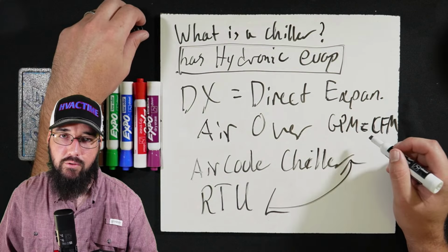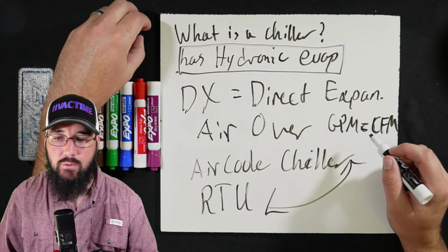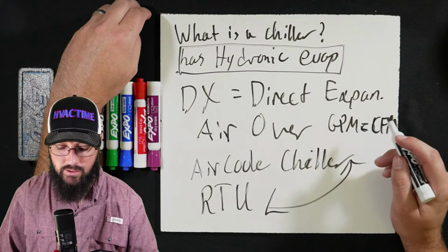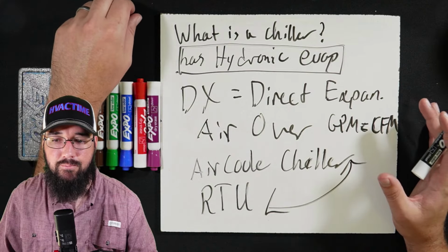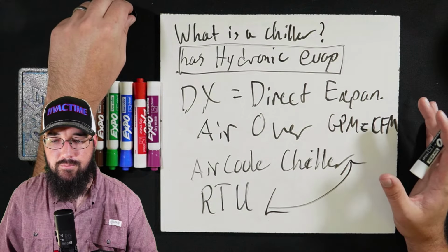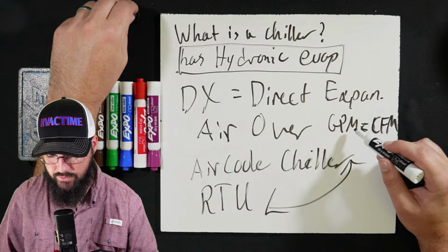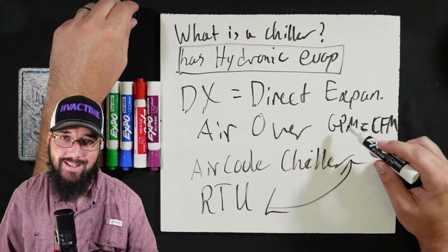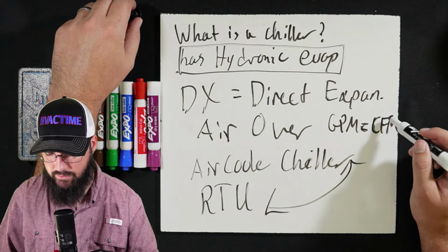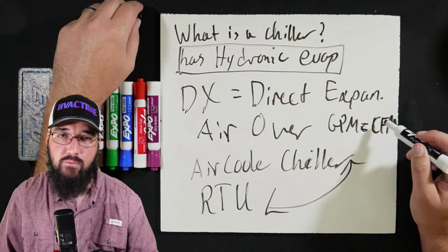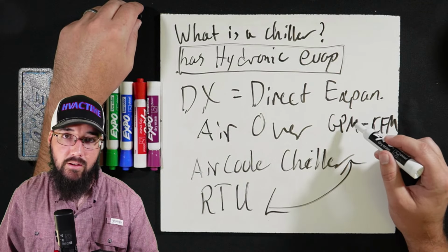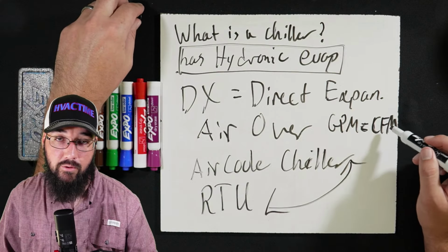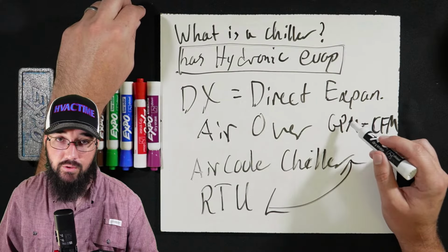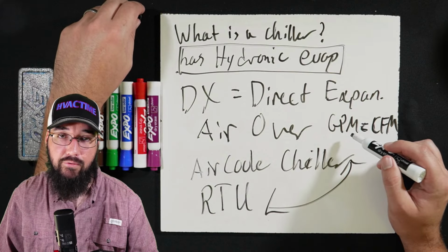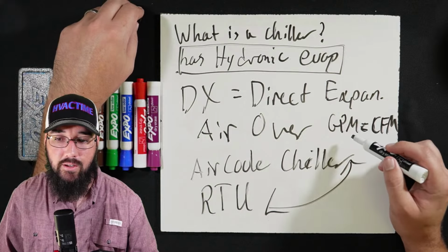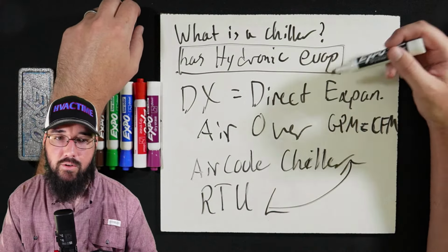The troubleshooting we go through, the conditions we will see, why we're going to test things a certain way, so much of that process stays the same. So much of it. It's just we're trading, instead of cubic feet per minute, it's gallons per minute. Instead of a vapor that we're moving through with a blower, and what's funny about this, a centrifugal blower motor, right? It's still centrifugal versus a centrifugal water pump moving a liquid fluid at GPMs. That's all we're discussing here.